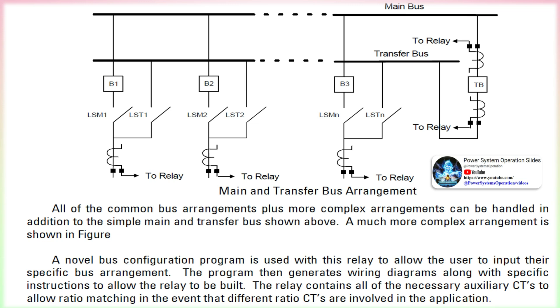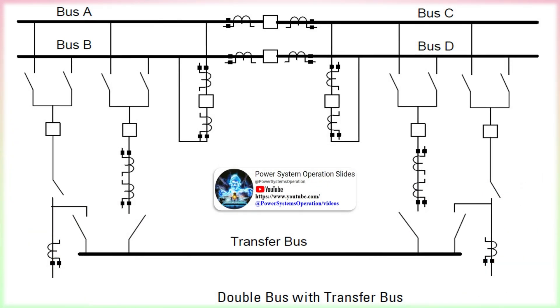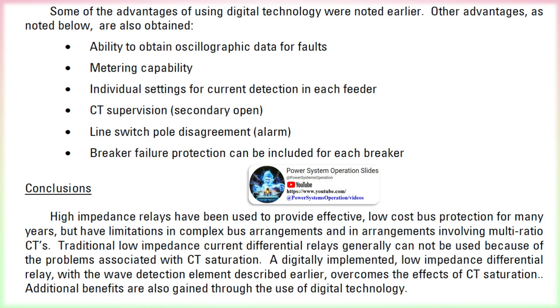In some bus arrangements, it is common to switch lines to different buses to facilitate operation and maintenance. In this arrangement, the tiebreaker (TB) is connected to one of the lines through the transfer bus while the regular line breaker is removed from service. Switching is accomplished via the line switches (LS). In the low impedance differential relay, auxiliary switches A and B associated with the line switches are brought into the relay, and the state of these switches is used to determine which breakers are connected to which bus so that the correct differential zones can be established. The CTs are always connected to the relay, so CT switching is not required because the zone of protection is determined via software. Separate trip outputs are provided for each breaker, so only those associated with the faulted bus will be tripped — one relay can protect multiple buses.